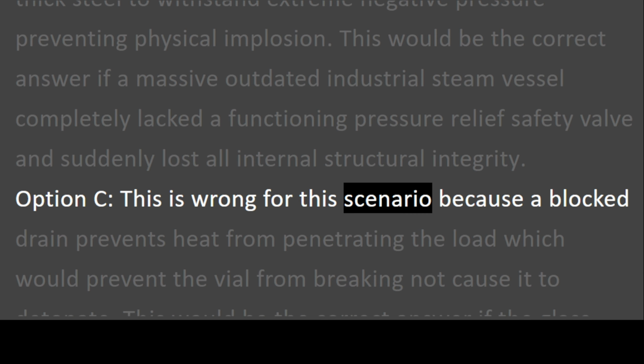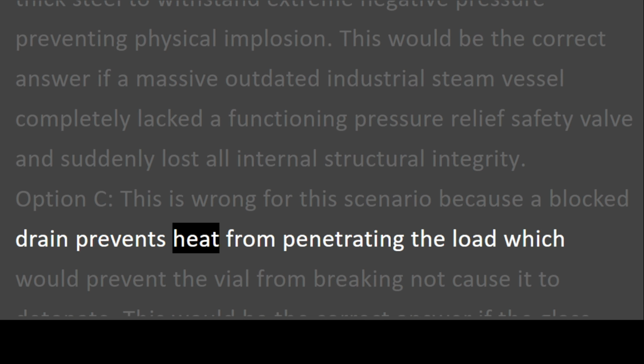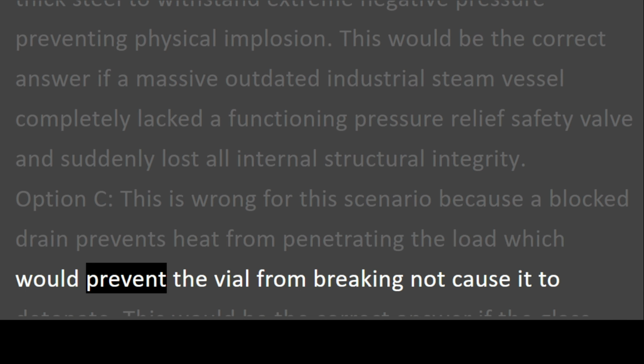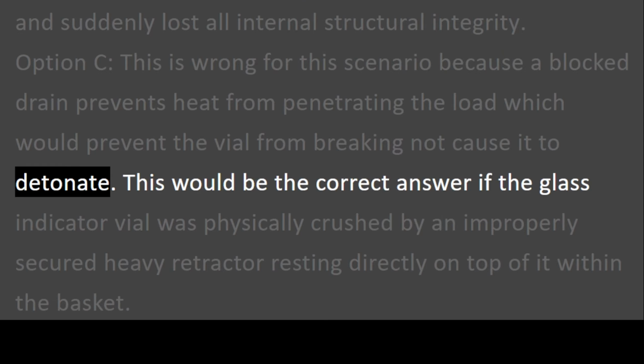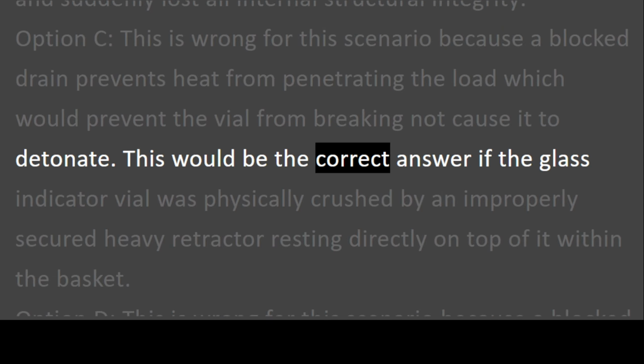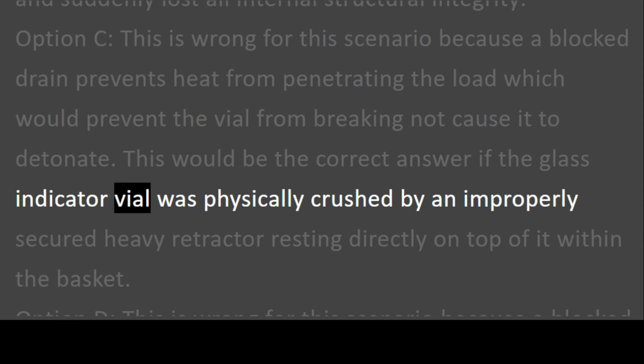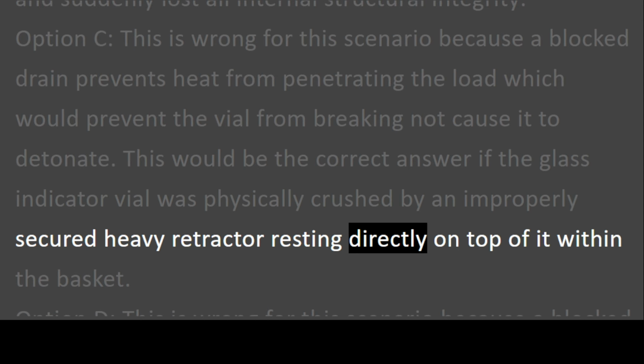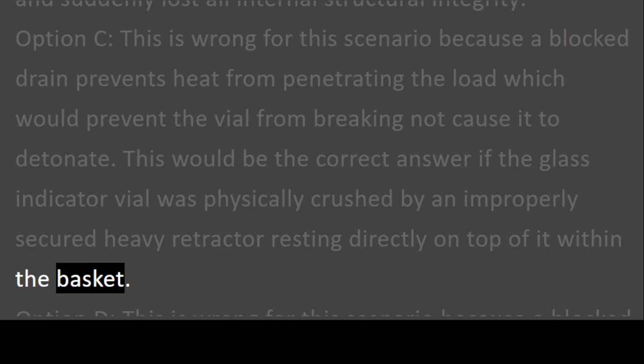This is wrong for this scenario because a blocked drain prevents heat from penetrating the load, which would prevent the vial from breaking, not cause it to detonate. This would be the correct answer if the glass indicator vial was physically crushed by an improperly secured heavy retractor resting directly on top of it within the basket.